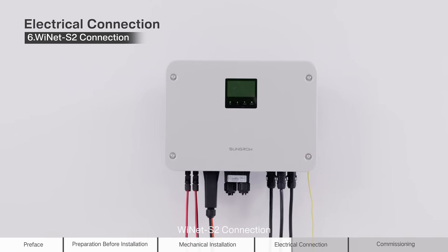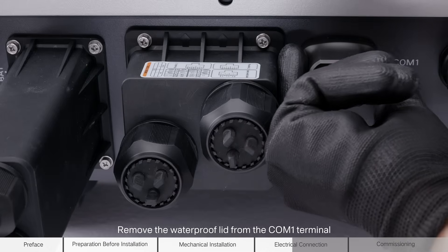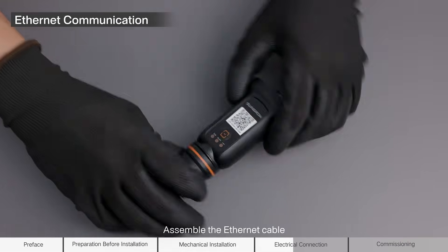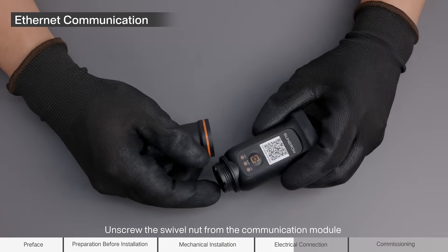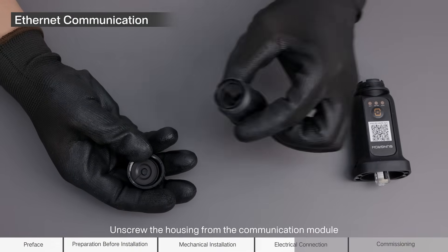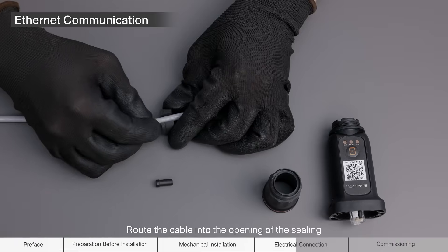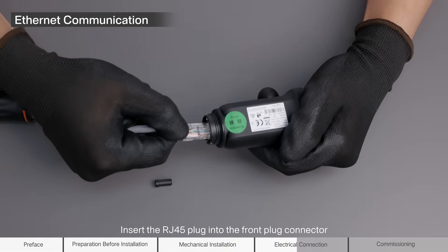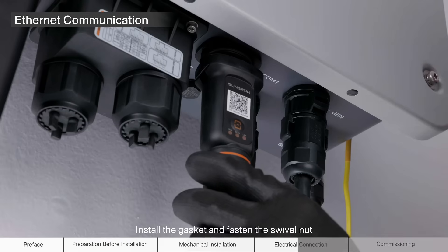WiNet-S2 connection. Remove the waterproof lid from the COM1 terminal. Ethernet communication: assemble the Ethernet cable. Unscrew the swivel nut from the communication module and take out the inner sealing ring. Unscrew the housing from the communication module. Thread the network cable through the swivel nut and gasket. Route the cable into the opening. Insert the cable through the housing. Insert the RJ45 plug into the front plug connector. Install the gasket and fasten the swivel nut.